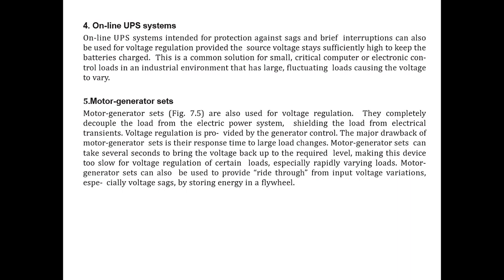So this is another method, where we use a motor generator set. If the voltage drops, it is sensed by sensors, which give an input to the motor. The speed of the motor needs to increase, and as the motor and generator are coupled with each other, the speed of the generator also increases. In that case, ultimately by using excitation windings, we can increase the voltage levels. But this is a time consuming method, so most probably it is not used. And then there is the cost. Costing is higher, because if you want to maintain the voltage of a particular piece of equipment, you again require two different devices such as a motor generator, which becomes very costly. That's why we are not going for such devices, that is, the motor generator set.